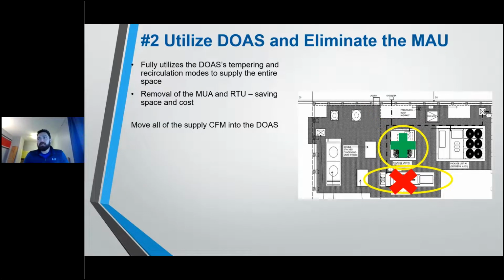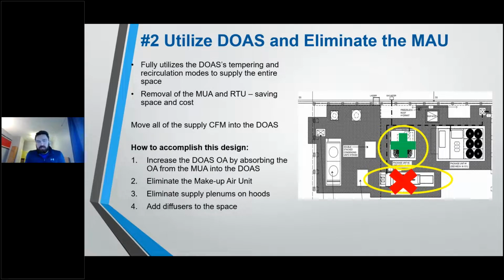Or we could fully utilize that DOAS's tempering and recirculating modes, and we could just eliminate the makeup air unit, thus saving us on roof space. So in order to accomplish this, we're going to move all of the air into the DOAS unit. We're going to eliminate the supply plenums at the hood, because now that we're utilizing DOAS, you don't want to dehumidify that air and then immediately exhaust it. So you don't want to bring it in at those ASP plenums. So we're going to add diffusers to the space, and we're eliminating those supply hoods.